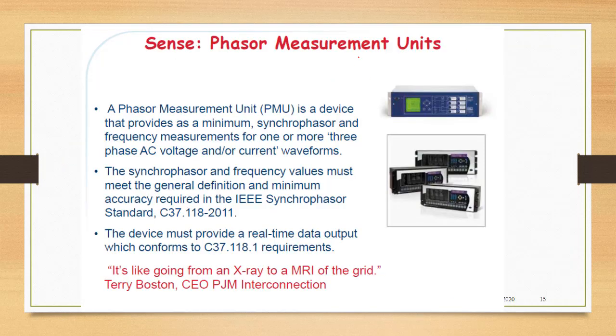Now a little bit we'll talk about the phasor measurement unit, which sometimes comes as an external device and sometimes is embedded with the IED, the intelligent electronic device. So a phasor measurement unit is a device that provides, as a minimum, synchrophasor and frequency measurements for one or more three phase AC voltage and or current waveforms. So it measures the synchronized voltage and current waveforms.